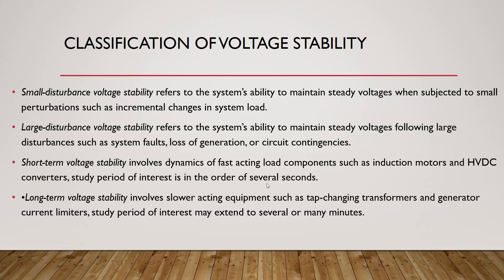Number four is long-term voltage stability, which involves the dynamics of slower-acting equipment such as tap-changing transformers — where changing the number of turns takes a larger time — and generator current limiters, which represent field current limiters. These two types of equipment have a large time constant, meaning the period of interest may extend to several or many minutes. So long-term versus short-term depends on the time constant of the equipment.